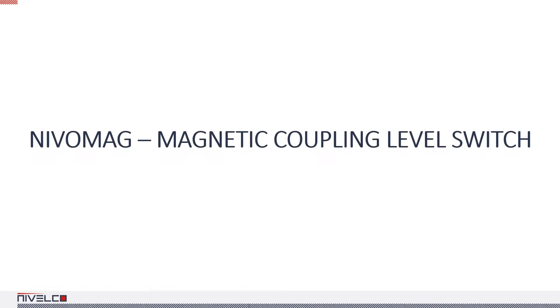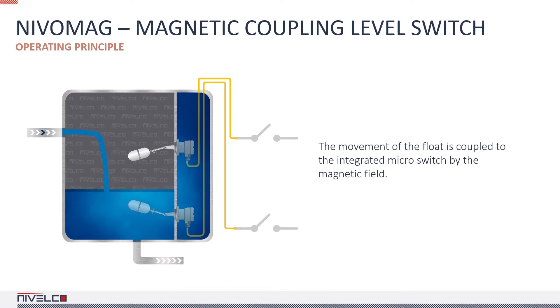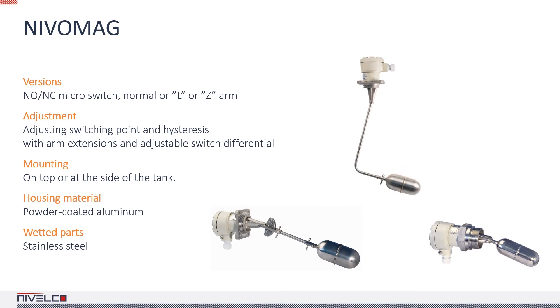NIVOMAG MK200 magnetic float level switches are used for point level detection and level control of liquids in all types of vessels. The float's magnet activates the output switch via a non-contact coupling system. The NIVOMAG has numerous side and top mounted versions, further widening the versatility of the device. For simple jobs, fixed hysteresis models offer an affordable solution, while for more complex level control applications, the right choice is the adjustable hysteresis variants. Models with rubber and silicone sleeves can be used with contaminated liquids. In addition, the NIVOMAG can be fitted with an MMK tester to check functionality even when the liquid's level is not changing. The housing of the electronics is separated from the tank space by a stainless steel wall, so the medium cannot come into contact with the electronic components.